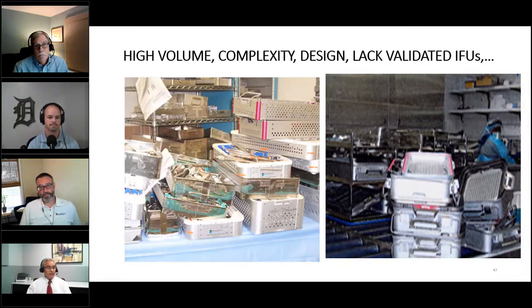If the manufacturer hasn't done some of that in-use cleaning process, this is a good time for that, because you really need collaboration between the healthcare setting and the manufacturer. When they made that device and went through the 510K clearance, they didn't really have access or couldn't bring it into the hospital for clinical use. So this is a good time to validate your IFU, verify that it's working, and be part of that purchasing process.